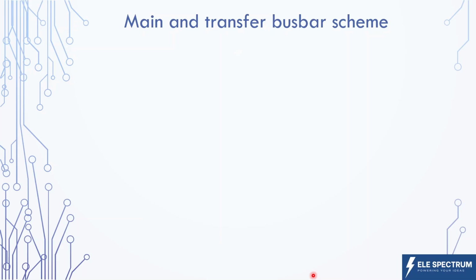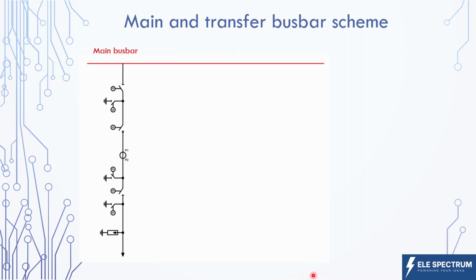That is the main and transfer bus bar scheme. We will again take the basis of the single bus bar scheme here. Let me tell you, there is redundancy for the circuit breaker. That means we can do the maintenance of the circuit breaker without interrupting power supply. Now to do this, we need a special bus bar which is called the transfer bus bar. This bus bar is only used for the transfer of power to the main bus bar, and at a time only one feeder can be connected to this transfer bus bar.